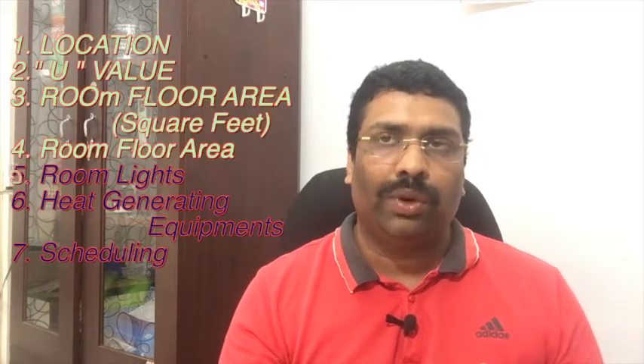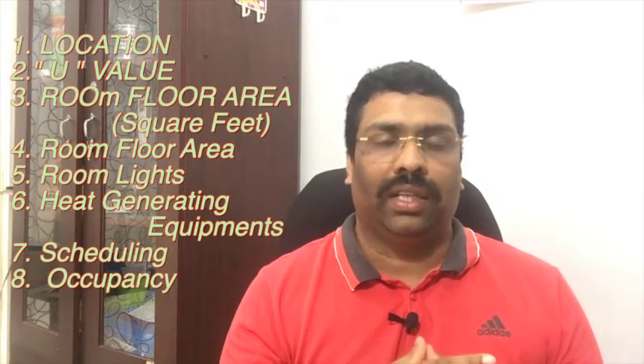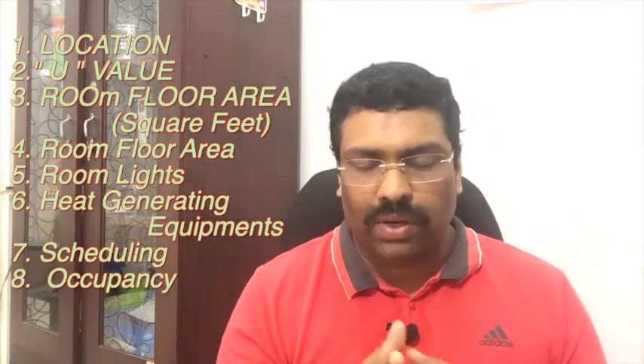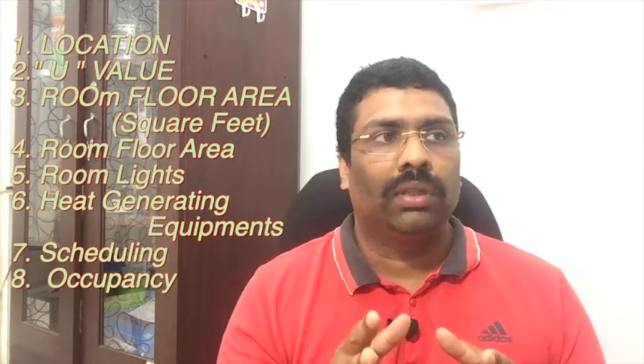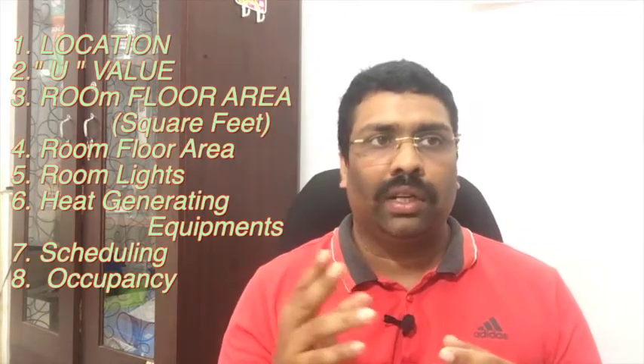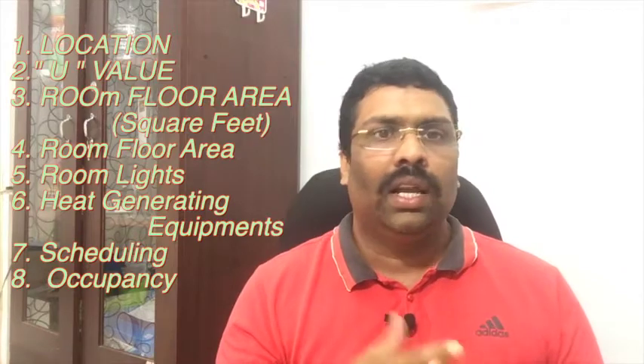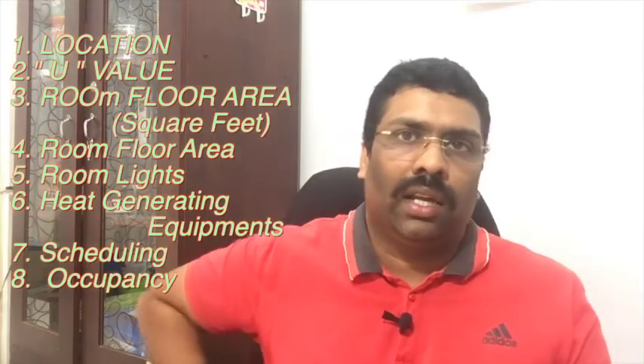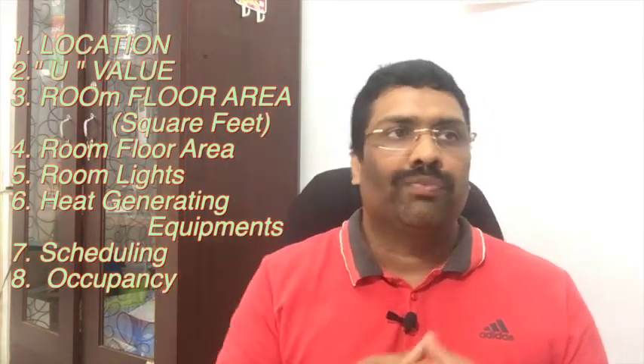And the eighth point is occupancy. Occupancy means how many people are there in the room. For occupancy, there is a schedule available from ASHRAE. For example, a bedroom has 2 people and a living room has 4 people. That kind of schedule is available in the ASHRAE handbook that we can consider.